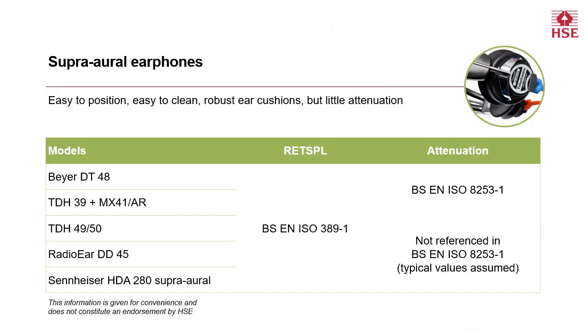For supraoral earphones, the RETSPLs are available in BS EN ISO 389-1. The attenuation values for the DT48 and TDH 39 and 49 models are given in BS EN ISO 8253-1. There are a couple of newer models of supraoral earphone available which are not referenced in this standard, but typical attenuation values for these can be assumed. Despite having low attenuation, supraoral earphones are easy to position, easy to clean, and tend to have robust ear cushions, if you can call them cushions.